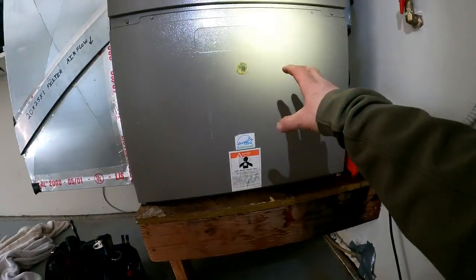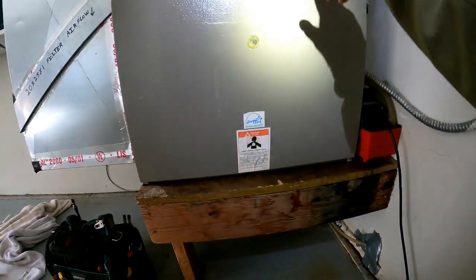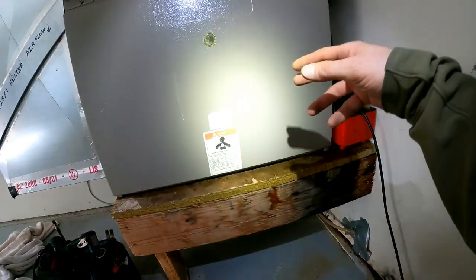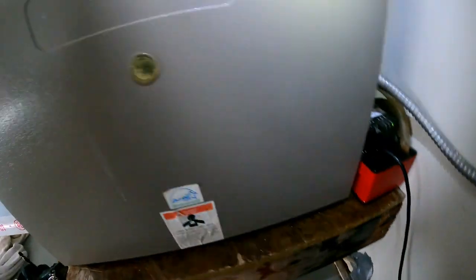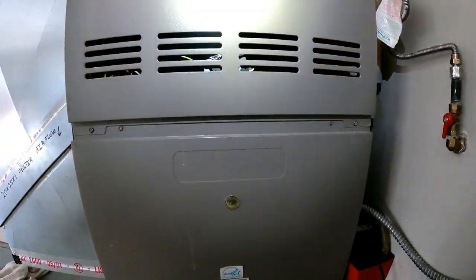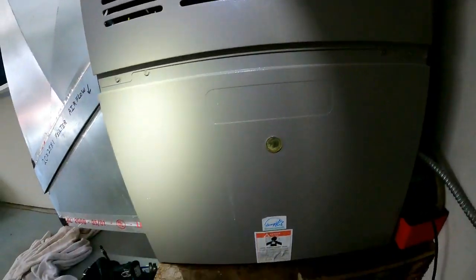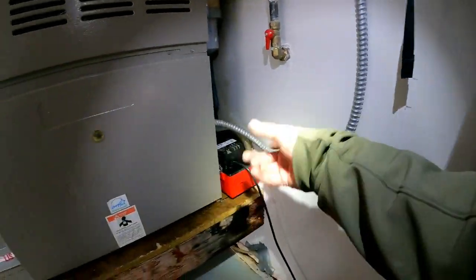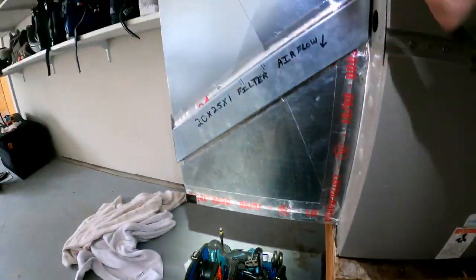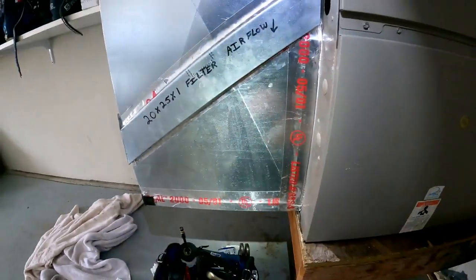It could be leaking from inside here somewhere too - maybe that heat exchanger is leaking down underneath. So I am going to just open the furnace up, because if that has a small crack, it could take a while to show. Let's open the furnace and see what we see there.